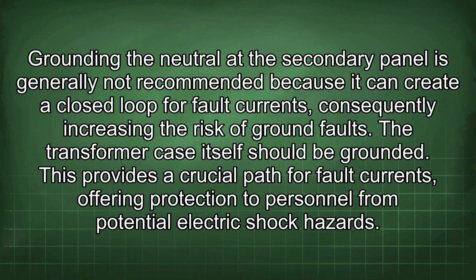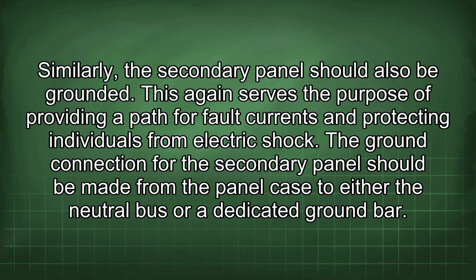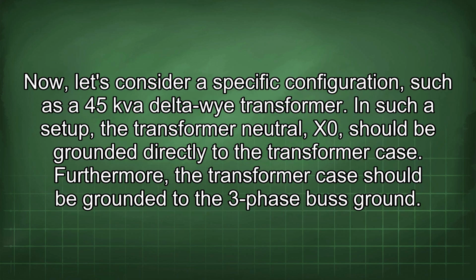The transformer case itself should be grounded. This provides a crucial path for fault currents, offering protection to personnel from potential electric shock hazards. Similarly, the secondary panel should also be grounded. This again serves the purpose of providing a path for fault currents and protecting individuals from electric shock. The ground connection for the secondary panel should be made from the panel case to either the neutral bus or a dedicated ground bar. Now let's consider a specific configuration, such as a 45 kVA delta-wye transformer.